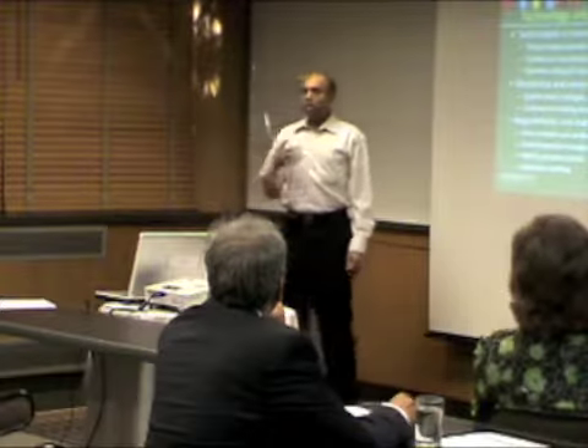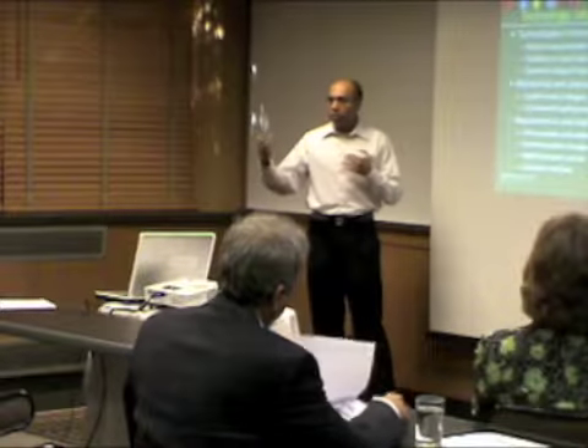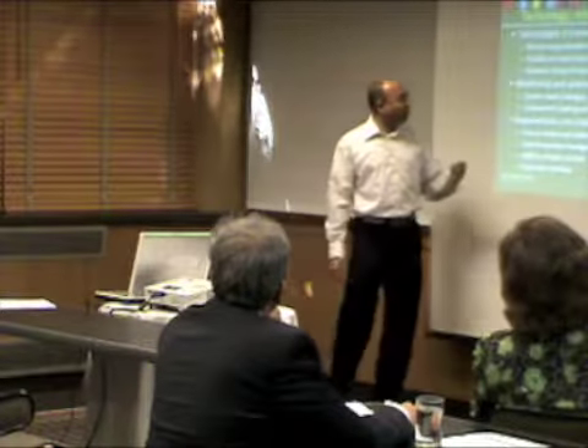Dynamic rating of transmission equipment means that equipment was originally rated at the time it was designed based on worst-case operating conditions. But if you're able to monitor operating conditions through a smart communication and measurement system, you may be able to calculate in real time the actual capacity of these transmission components. Sometimes you can squeeze an extra 30% capacity out of them if conditions are favorable, which helps because it defers capital spending.